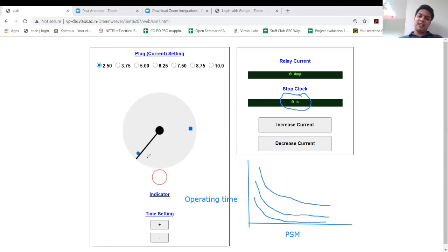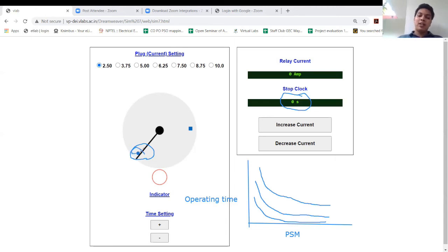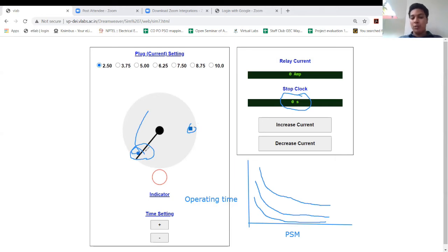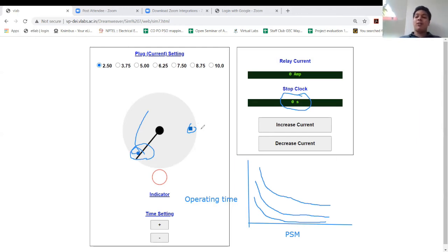By adjusting the time setting dial, you are adjusting the backstop position. When you increase the time setting, you are moving the backstop further, increasing the distance the movable contact must travel. When the movable contact touches the trip contact, the circuit breaker operates. This is the way to conduct this experiment.